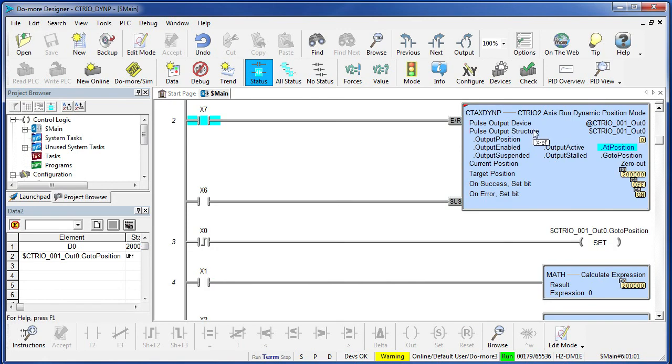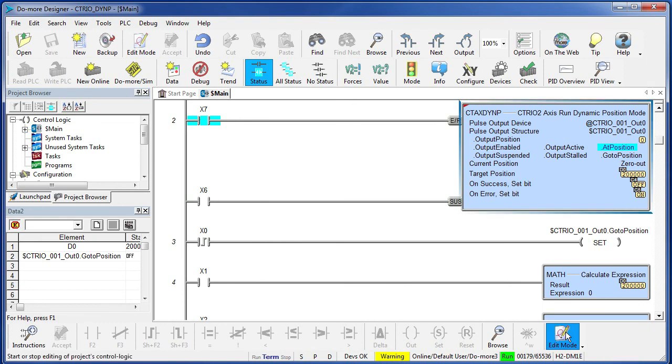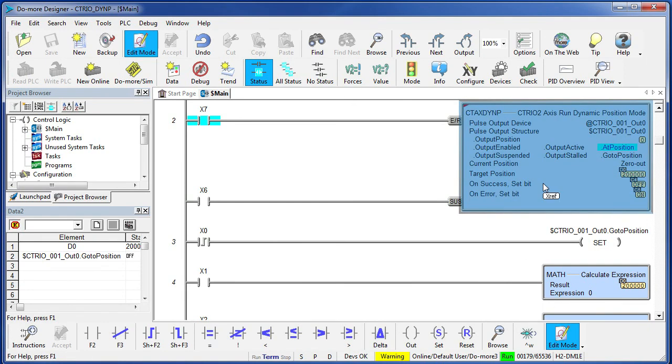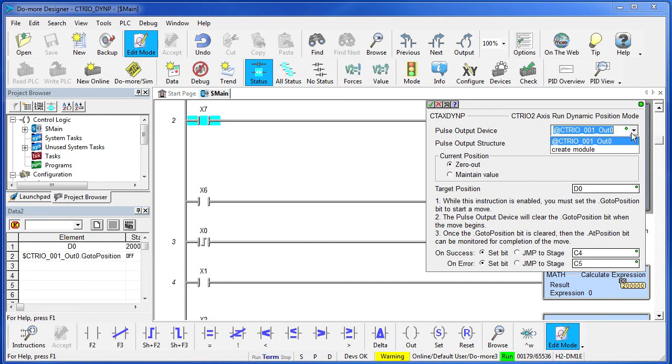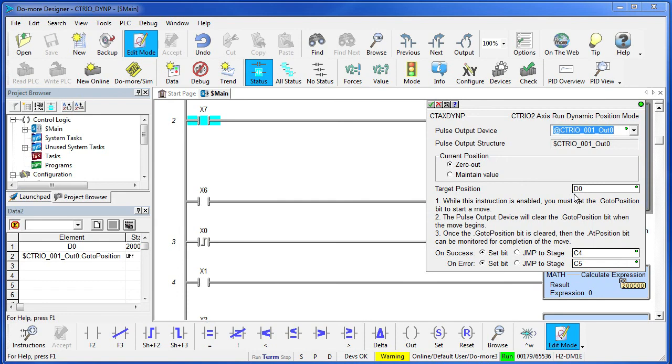On the next rung I have the Dynamic Position block. I have already put it in here to save us some time, so let's go take a look at it. All we do is select the module we want to talk to – of course we only have one in this system. Do we want to zero out the position when we first call this routine? We do in this example. And we give it the register that we are going to use for the target position.